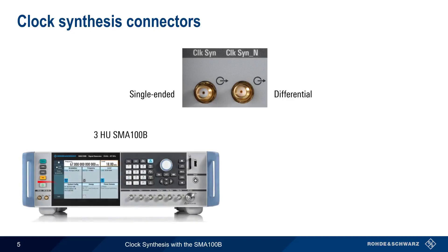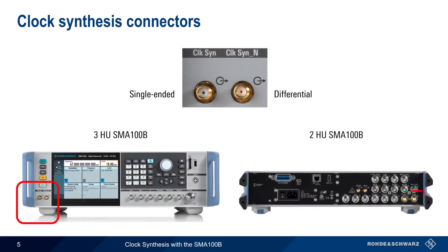Let's start with connections. The clock synthesis option provides two SMA connectors. The one on the left is used for single-ended signals, and both are used when generating differential clock signals. These connectors are located on the front of the 3-height unit SMA100B, and on the rear of the 2-height unit SMA100B.